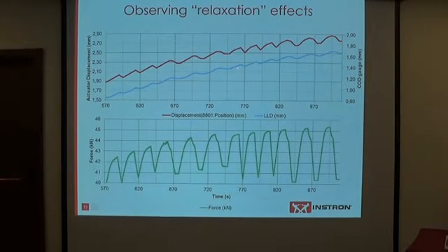And you see how we've got a very slopey shouldered blue line while we're controlling in position, and when we control in the COD gauge itself, we're forcing the actuator to conform and do some interesting tricks to keep up. So, demonstration of what's possible.